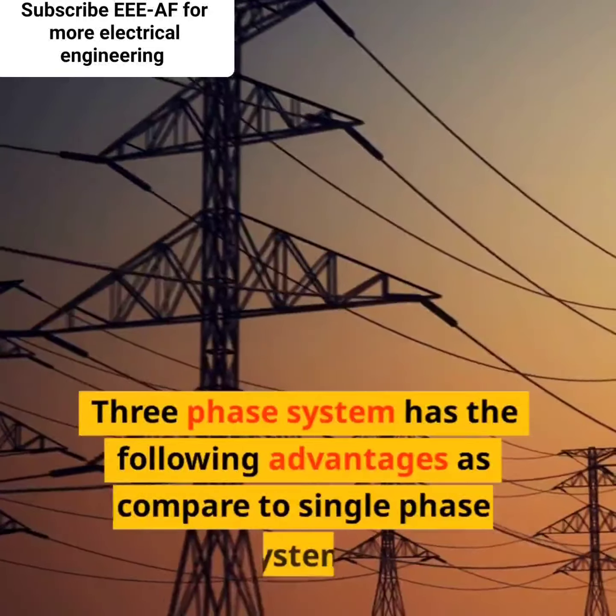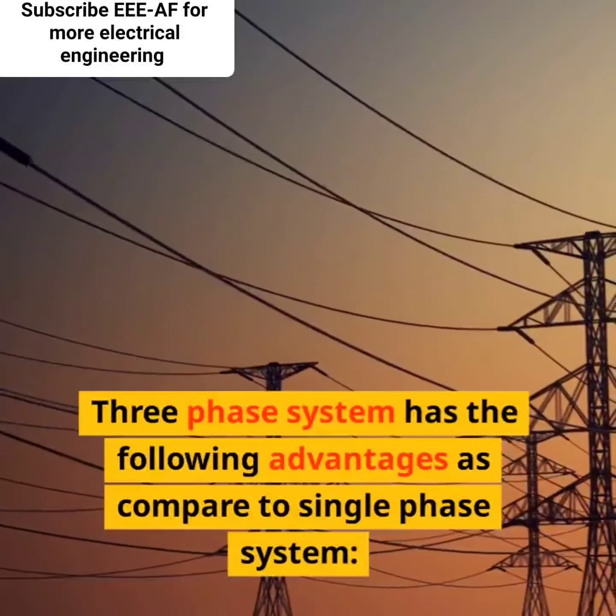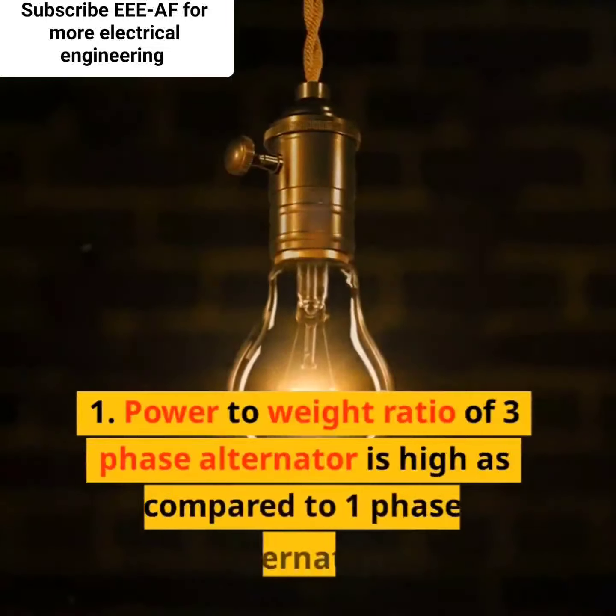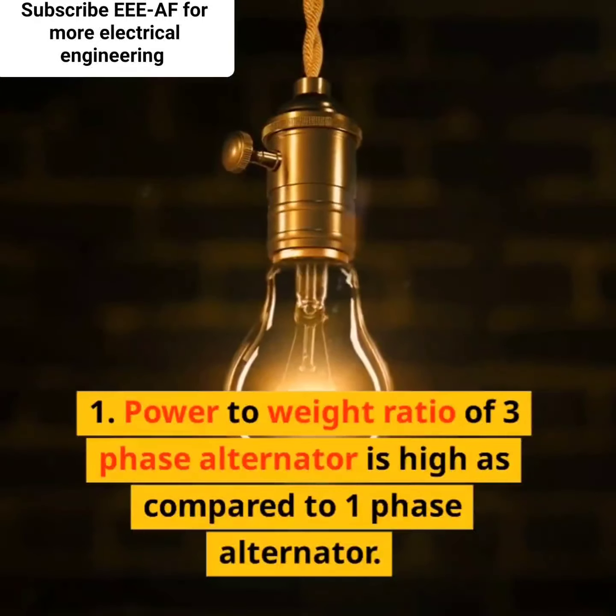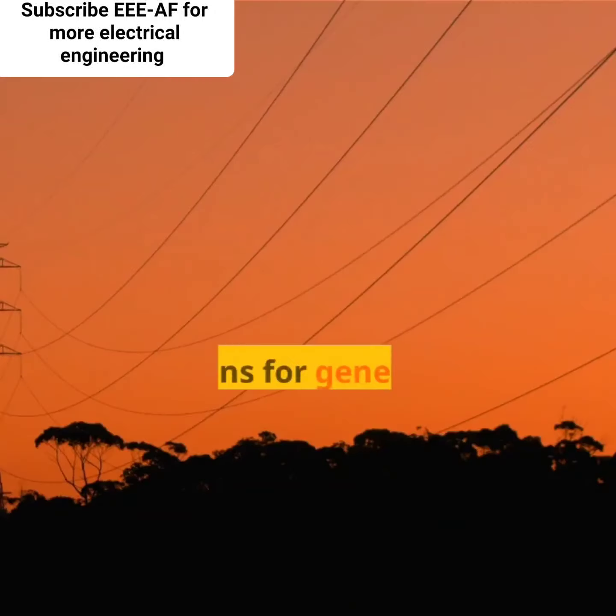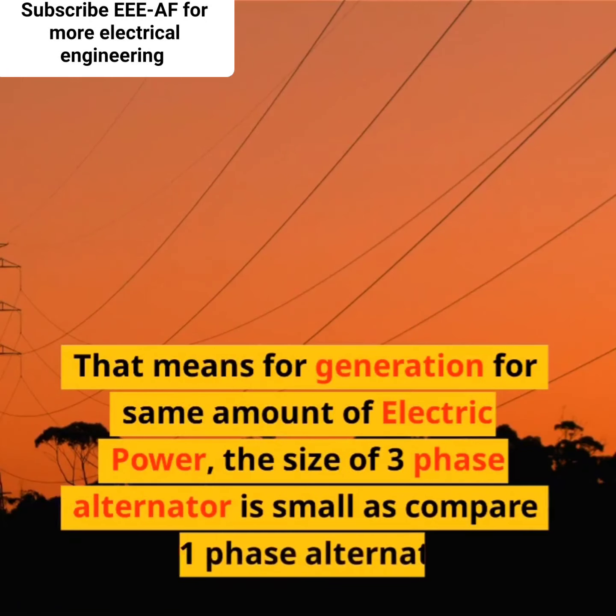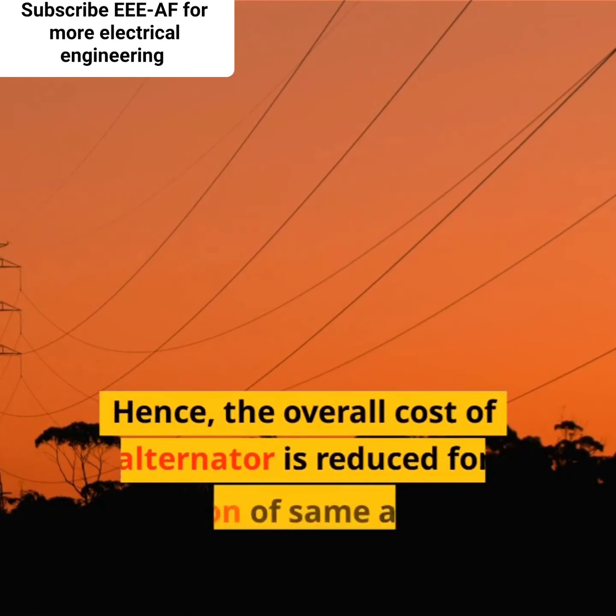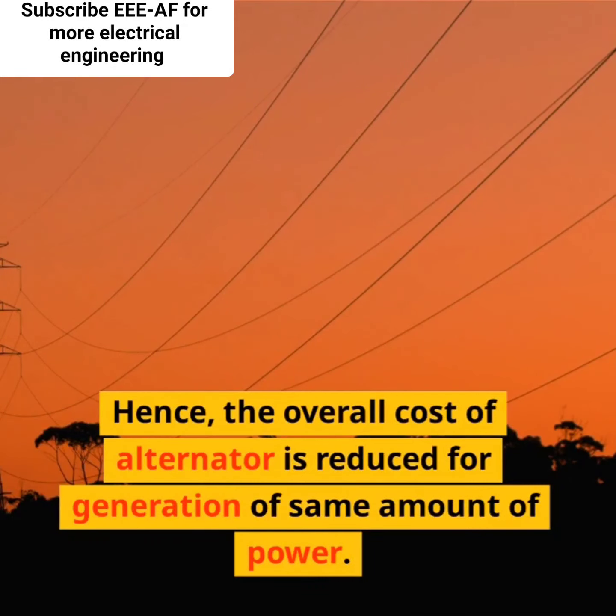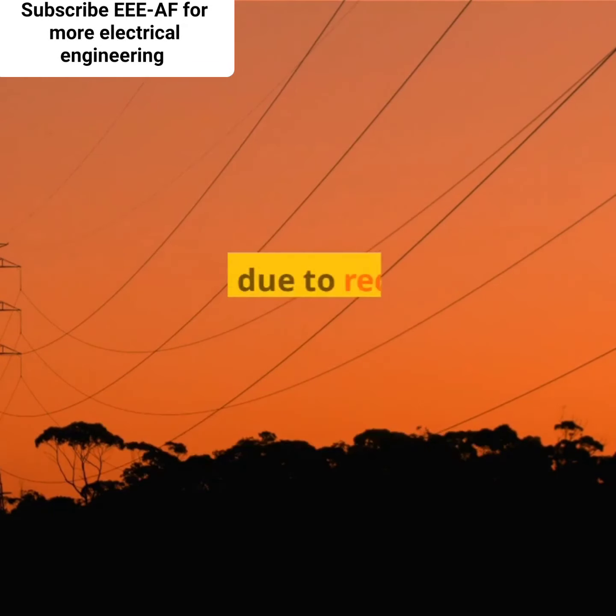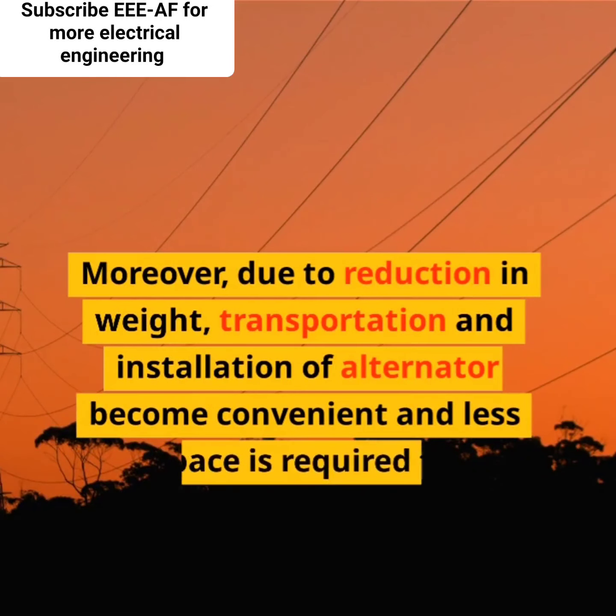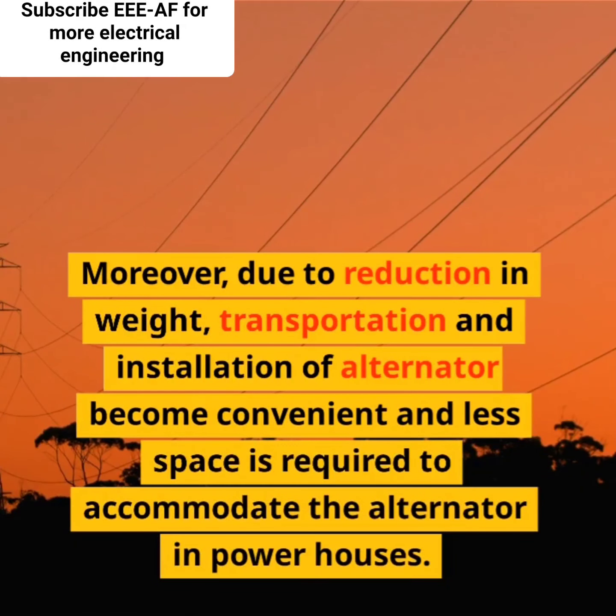Three-phase system has the following advantages as compared to single-phase system. 1. Power-to-weight ratio of three-phase alternator is high as compared to one-phase alternator. That means for generation of the same amount of electric power, the size of three-phase alternator is small as compared to one-phase alternator. Hence, the overall cost of alternator is reduced for generation of the same amount of power. Moreover, due to reduction in weight, transportation and installation of alternator become convenient and less space is required to accommodate the alternator in powerhouses.